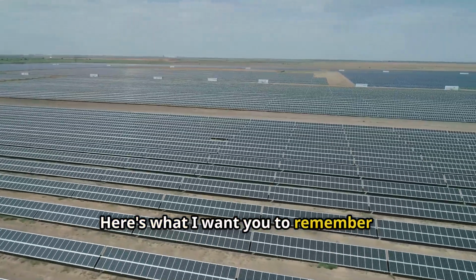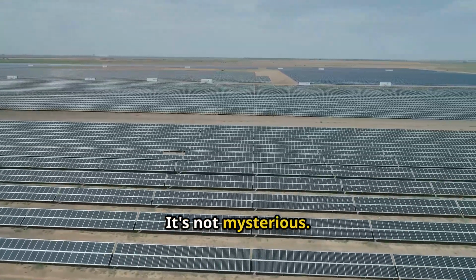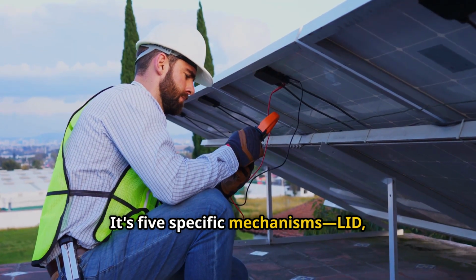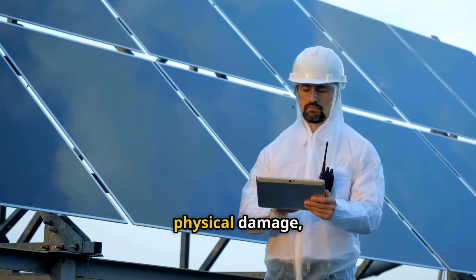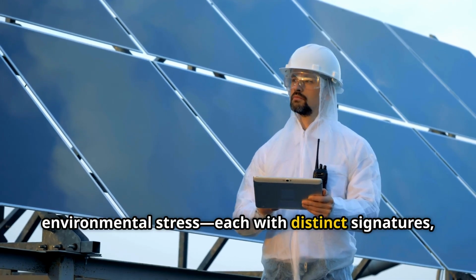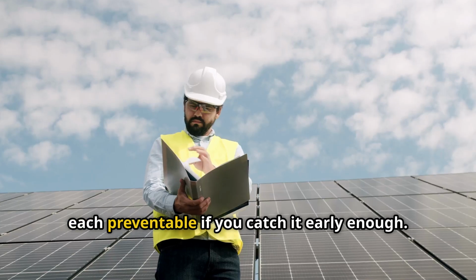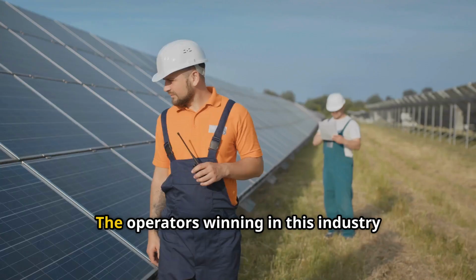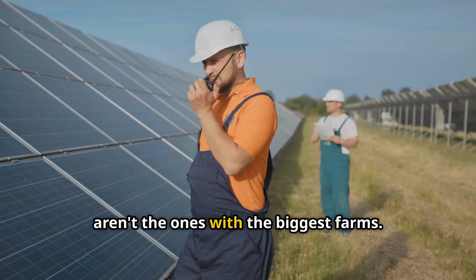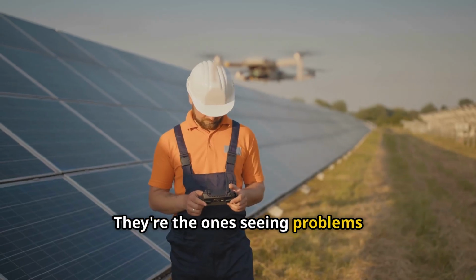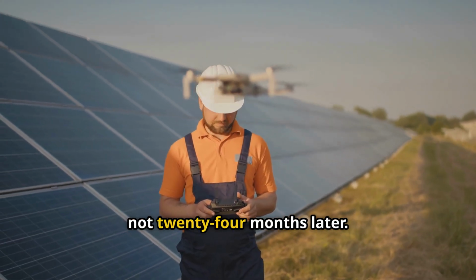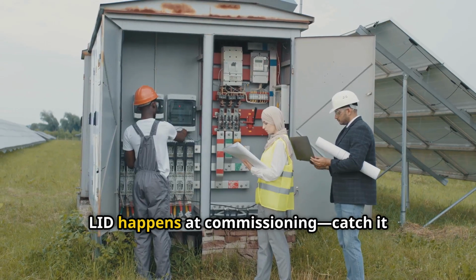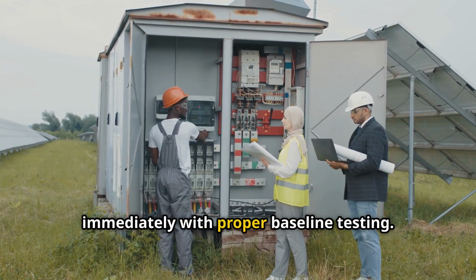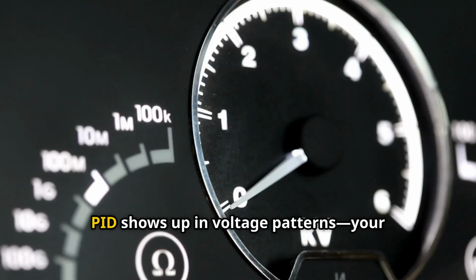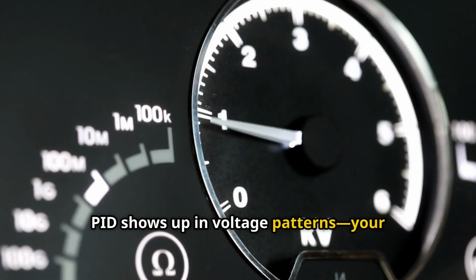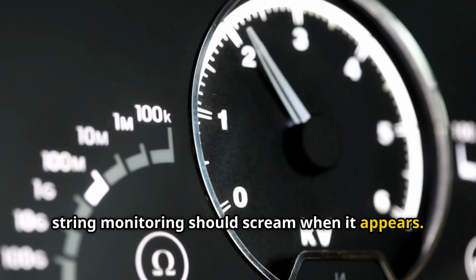Here's what I want you to remember: degradation is not random, it's not mysterious, it's 5 specific mechanisms: LID, PID, LETID, physical damage, environmental stress, each with distinct signatures, each detectable, each preventable, if you catch it early enough. The operators winning in this industry aren't the ones with the biggest farms, they're the ones seeing problems 24 hours after they start, not 24 months later. LID happens at commissioning. Catch it immediately, with proper baseline testing. PID shows up in voltage patterns, your string monitoring should scream when it appears.